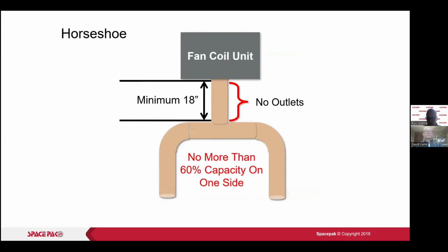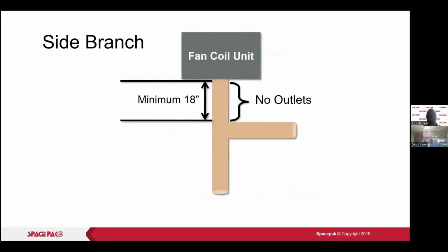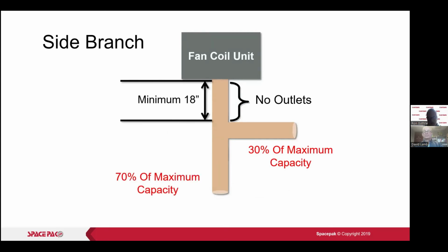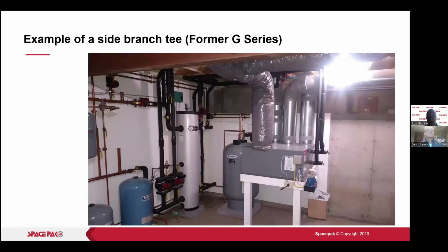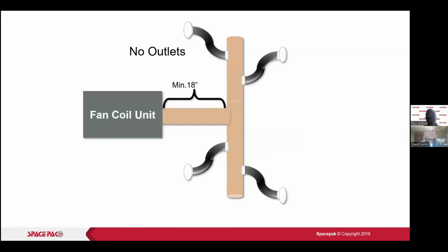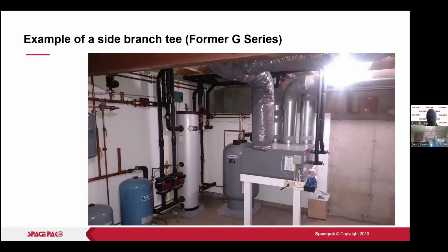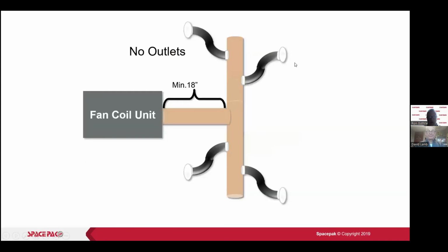All right, we got the 60-40 rule, no more than 60% capacity on one side. Again, the same applies with the minimum of 18 inches before any fitting, including a T that you're doing a shotgun off of. 30% maximum capacity. It doesn't have to be 30. It can be less than that, but maximum would be 30. And 70% down the main trunk, maximum capacity. All right, there's that. Again, that was a good side shot picture right there.